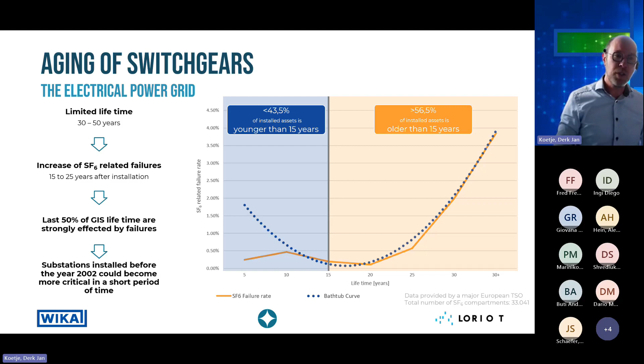When you look at the switchgears, we know that the average lifetime of a switchgear is between 30 and 50 years. And when you take a look at the curve over here, you can see that there is an increase of SF6 related failures after 15 to 25 years. And we know, based on the data that we received from one of the biggest European transmission system operators, that more than 56% of the installed base is older than 15 years. So that means that all the substations from the beginning of the year 2000 are becoming more and more critical in a shorter period of time. So we need to have a clear focus on these aging substations.